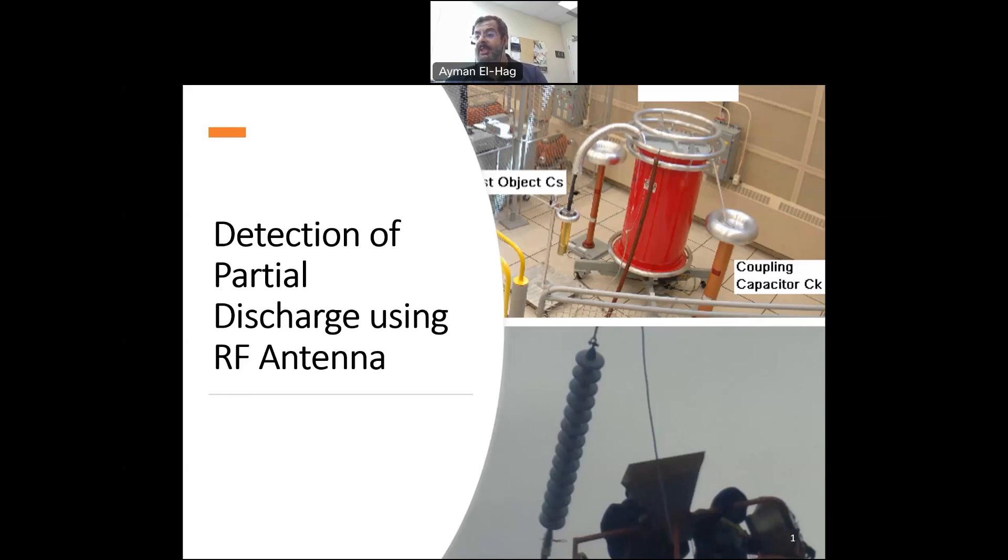However, this technique is intrusive and can only be used if you are inside the lab. Now if you are in the field and you want to detect partial discharge, you cannot have this setup, then you have to use a non-intrusive method. One of them is to use the RF antenna to detect the partial discharge.